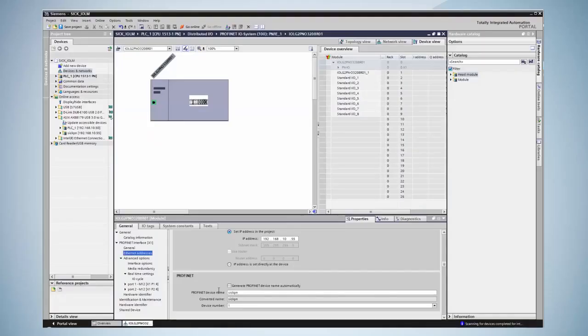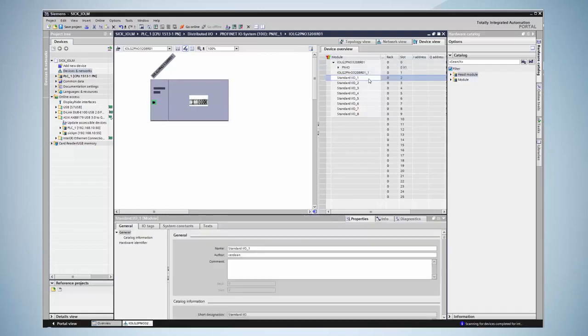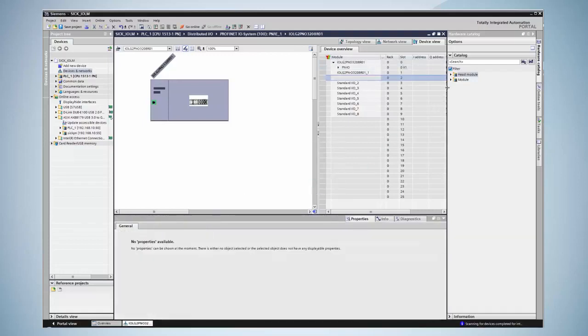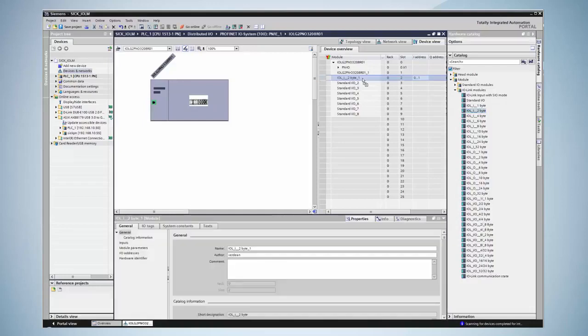The next step is the configuration of the IO-Link ports. On port 1 a SICK sensor is connected. In this example the standard IO module is deleted and replaced by an IO-Link module. As the connected sensor has a bit length of 2 bytes, a 2 byte module is selected. For process data access the PLC's IO addresses can be configured in this field.